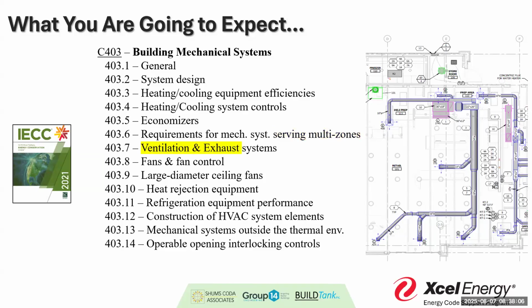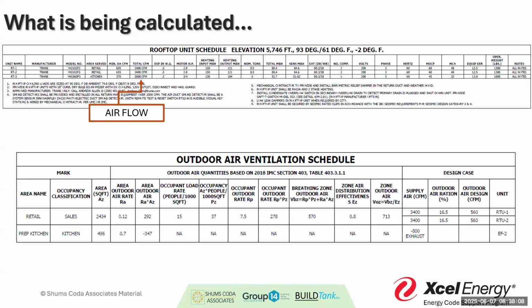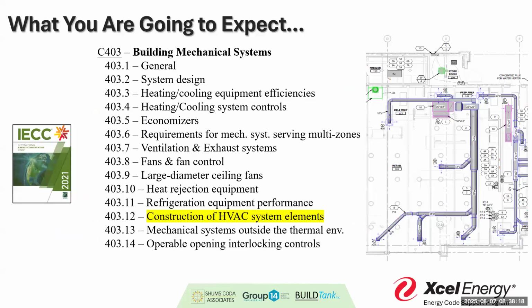Same thing with exhaust systems. I'm looking to make sure I have the appropriate airflow that matches my outdoor air ventilation schedule, and also making sure those fans, whether integrated or not, have the appropriate efficiency.